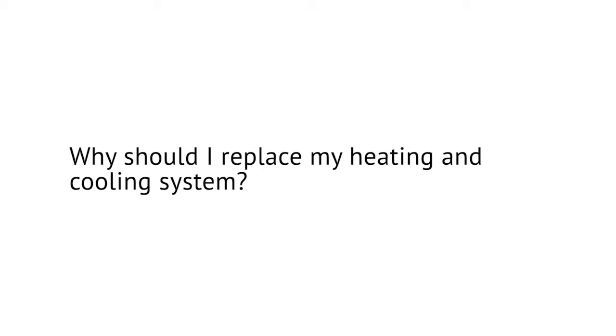Dirt and grime is one of the biggest factors in the breakdown of a system. So when we look at doing a thorough system rejuvenation on a unit, for the furnace, we're taking out the burners, we're cleaning those, we're actually adjusting gas pressures because that can determine what level of energy and gas your system is using, having it set at the appropriate gas pressure.